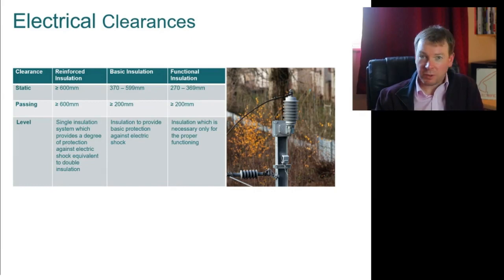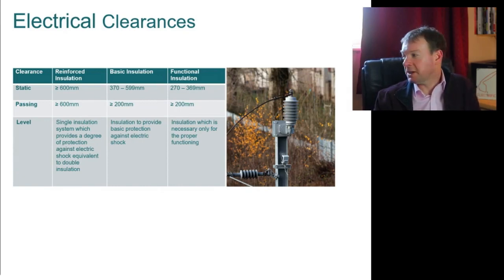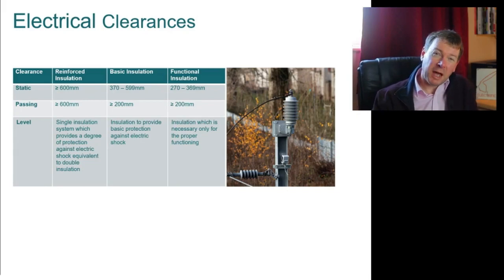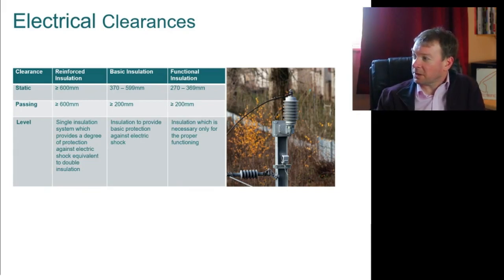Basic insulation we would use routinely. Functional insulation we would use, but we'd do some kind of risk assessment to make sure that's safe in that location. This table's a little out of date now, and I need to update it, because there are now further levels below functional insulation.